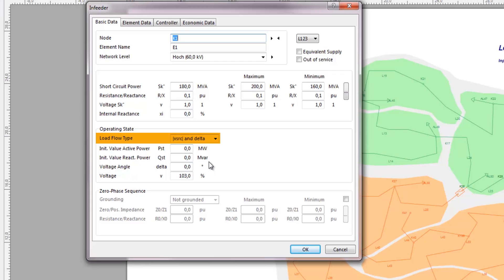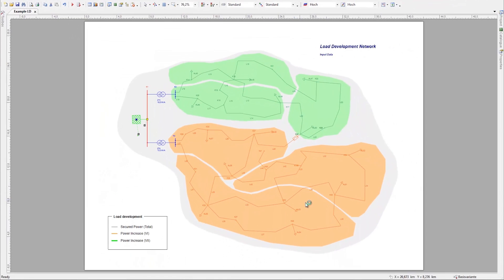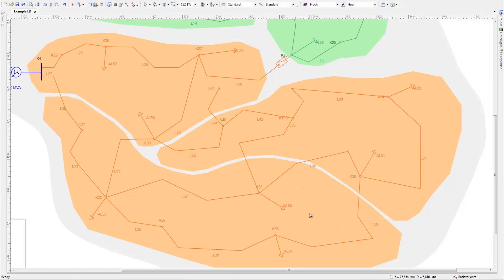In building the network, at least one slack generator is needed to balance the fault. This slack infeeder prescribes the voltage at a node and fulfills a balancing role, allowing power to be a result of the Load Flow calculations. Multiple slack generators are allowed. In case of islanding conditions, PSS SINCAL offers the option of switching the strongest generator over to a slack to provide the isolated network with power separately.